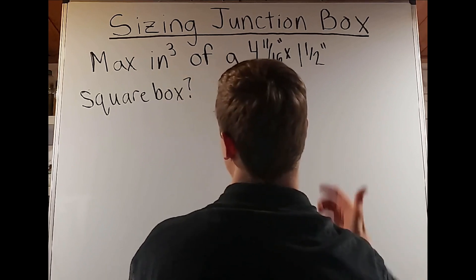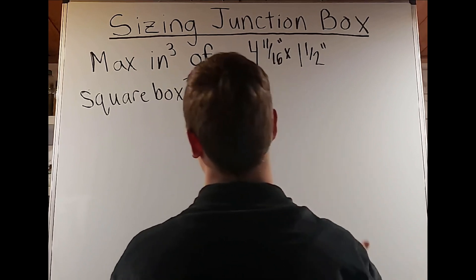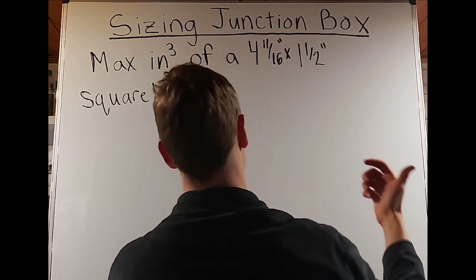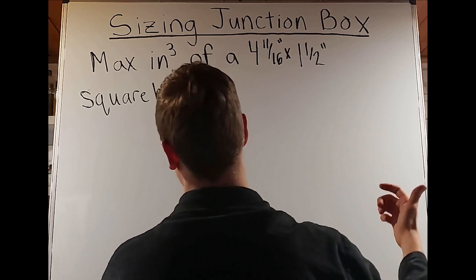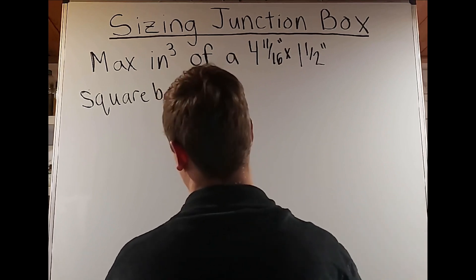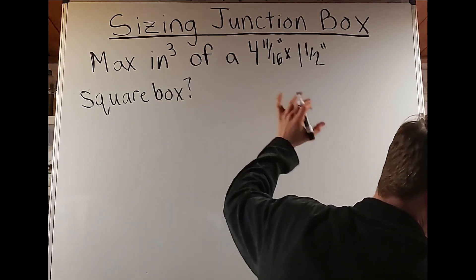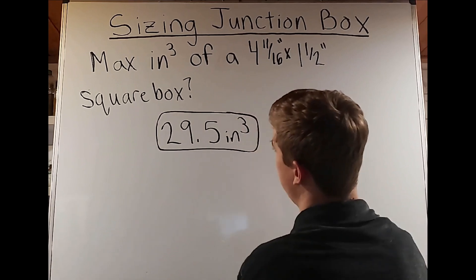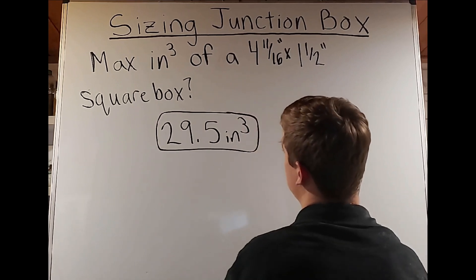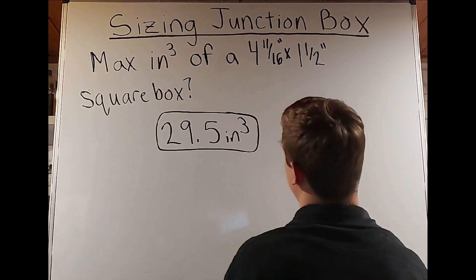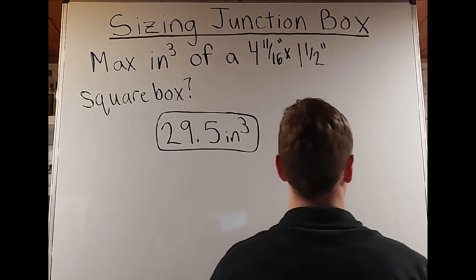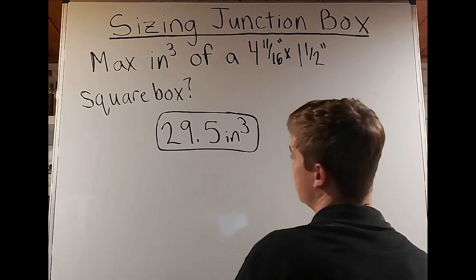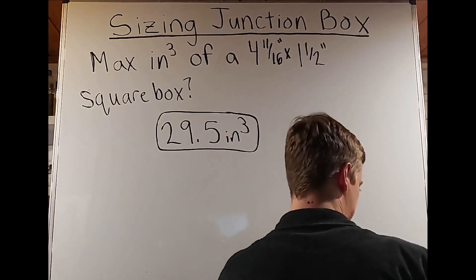Next: what is the maximum cubic inches of a four-and-eleven-sixteenths by one-and-a-half inch square box? We find that size under square box in the table and it gives us 29.5 cubic inches. We didn't have to do any math — we just had to look at the table. That's another very useful aspect of Table 314.16A.